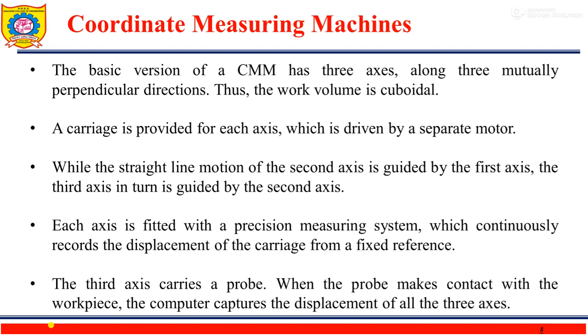The basic version of a CMM has three axes along three mutually perpendicular directions, so the work volume is cuboidal. A carriage is provided for each axis, driven by a separate motor. The straight-line motion of the second axis is guided by the first axis, and the third axis is guided by the second. Each axis is fitted with a precision measuring system that continuously records the displacement of the carriage from a fixed reference. The third axis carries the probe, generally the Z axis, and when the probe contacts the workpiece, the computer captures the displacement of all three axes.